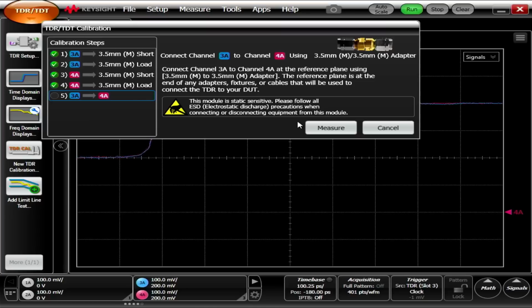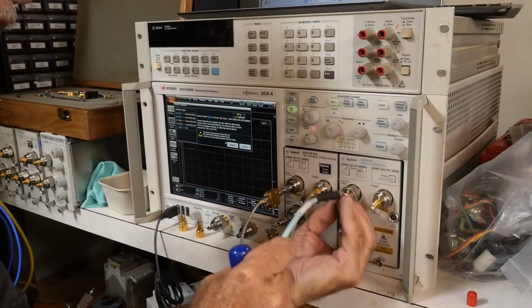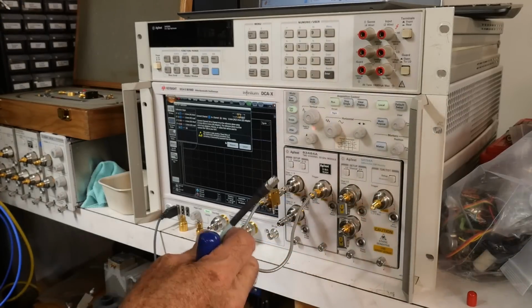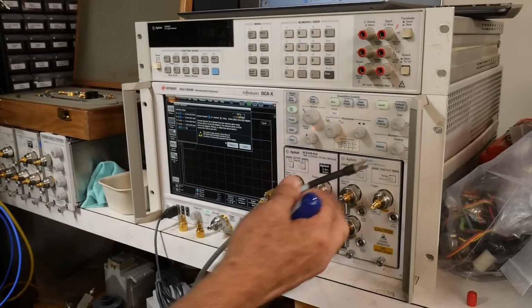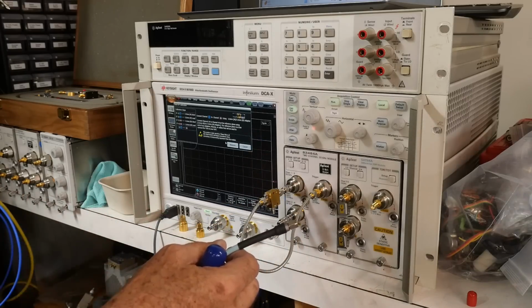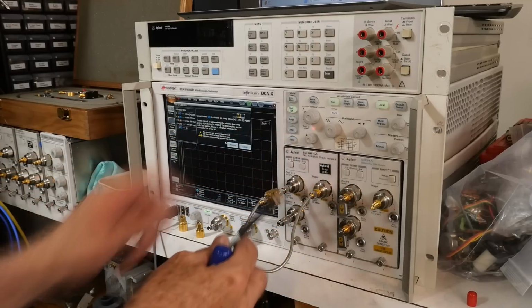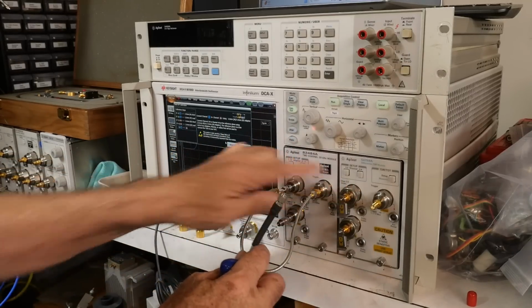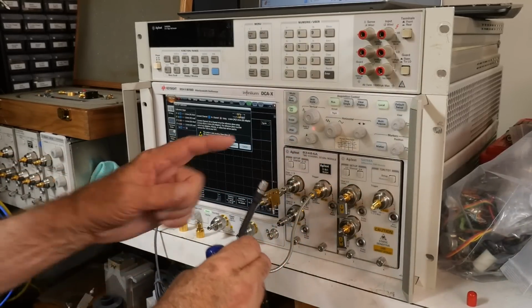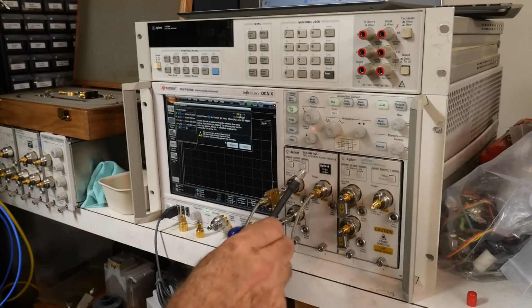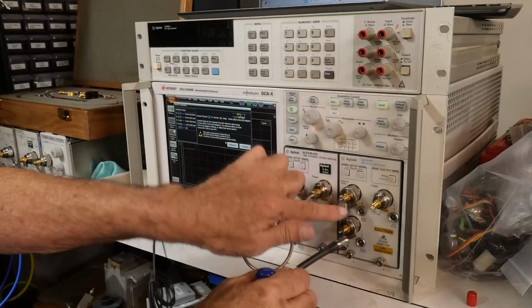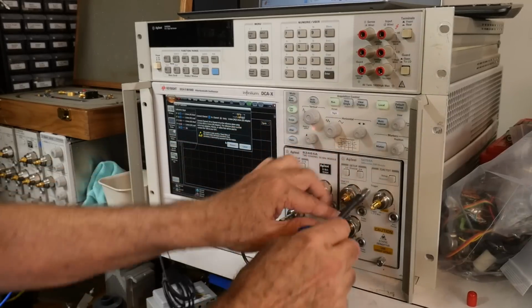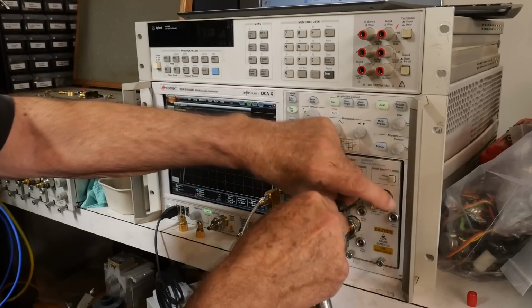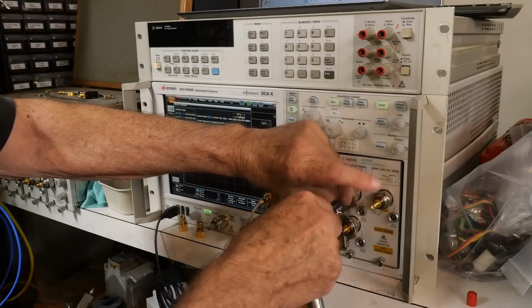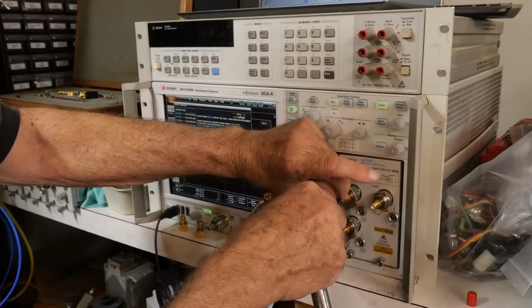So we will take one of the supplied cables. The reason these port covers are closed like this is because they're static sensitive. They say you should wear a wrist strap. I'm very careful to make sure I touch the instrument, but there's a little nub in here. One of the things you can get in trouble with is built-up charge inside your cable. If you touch the cable to that little knob, you can short out your cable and get rid of any charge that might be in it, acting as a capacitor.